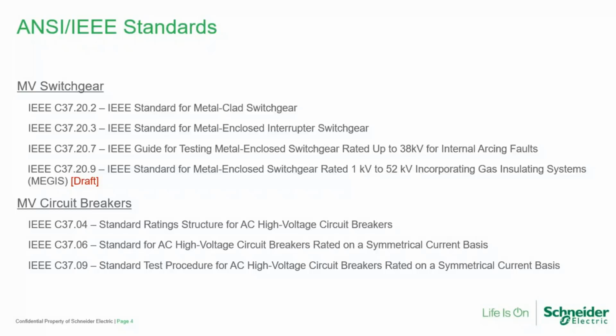Other important standards that need to be taken into consideration are the medium voltage breaker standards. C37.04 covers the rating structure for all medium voltage and high voltage circuit breakers, including continuous current, dielectric withstand, short circuit current, transient recovery voltage, capacitive switching, along with mechanical endurance, load current, and out of phase switching. C37.06 lists the preferred ratings for medium and high voltage circuit breakers, and C37.09 is the design and production testing procedures for medium and high voltage circuit breakers rated above 1,000 volts. So these medium voltage circuit breaker standards really apply across the board for the MV switchgear standards when it comes to using circuit breakers as opposed to fuse switch style interrupting or disconnecting.